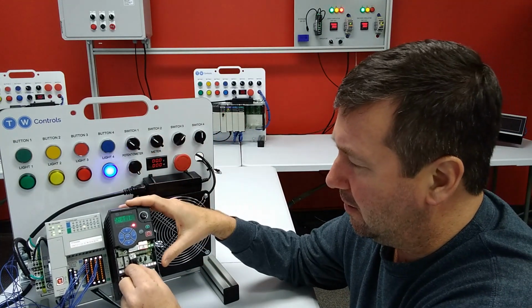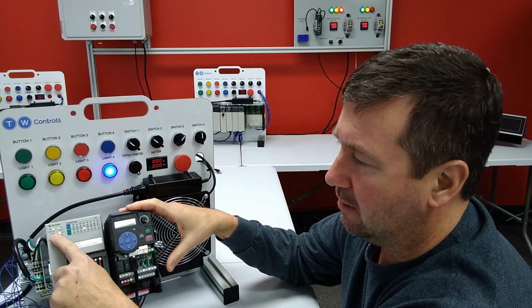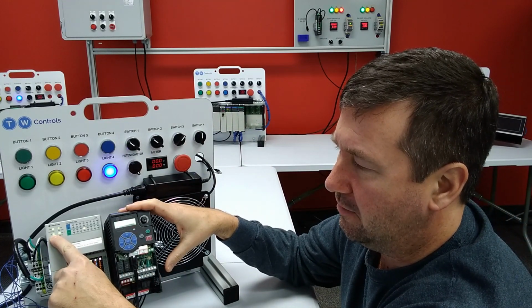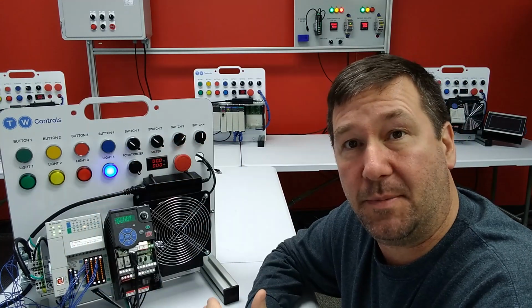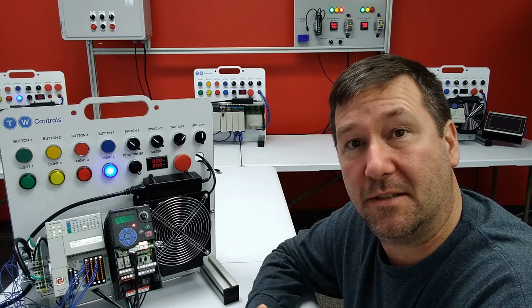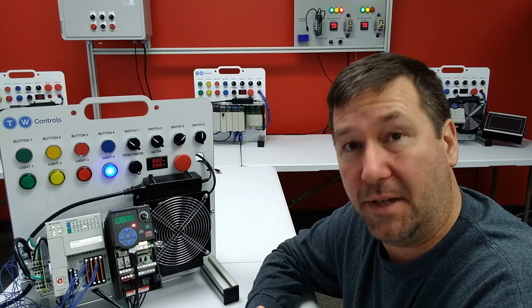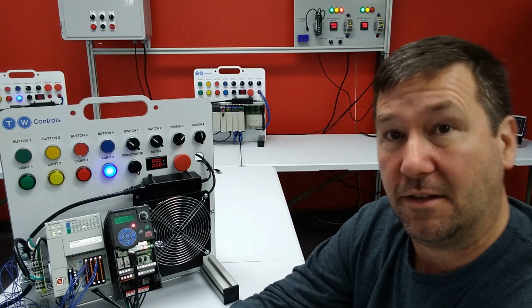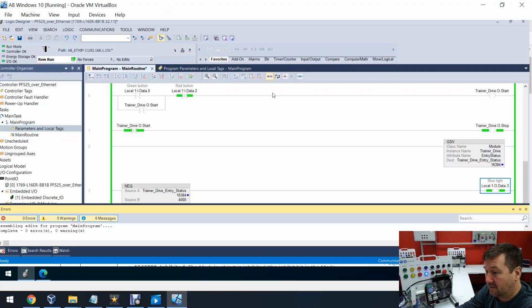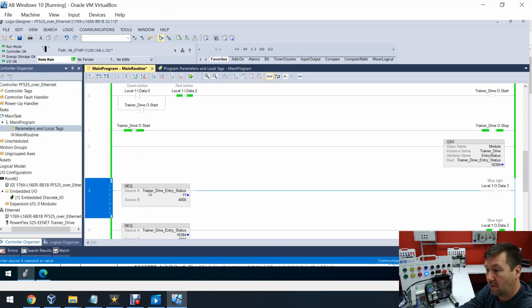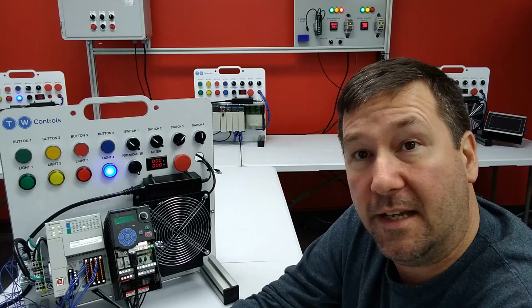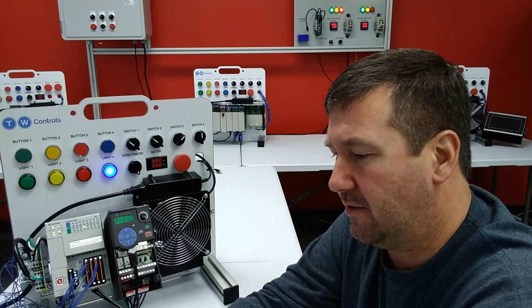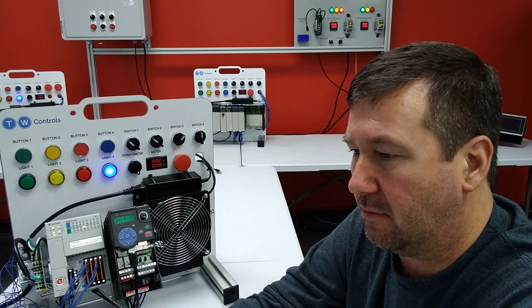All right, we're going to plug our cable in. We're going to wait for this I/O light to go off. And, oh, it's still on. This is because we entered that 4000 as a decimal, but it is supposed to be a hex number. So there are two ways we can fix this. First, we know that when we're running, it shows 16,384. We could simply put 16,384 right there, and that would work. Let's go ahead and do that, just so we see that it does work.